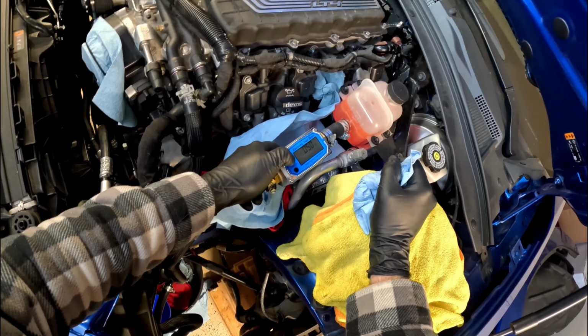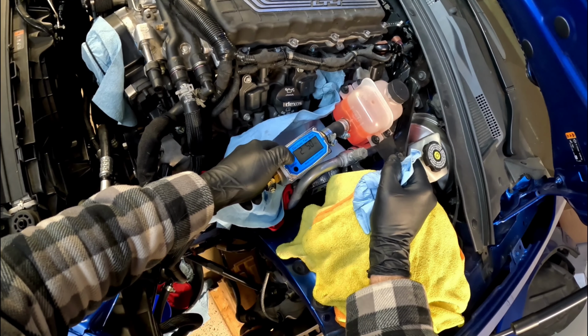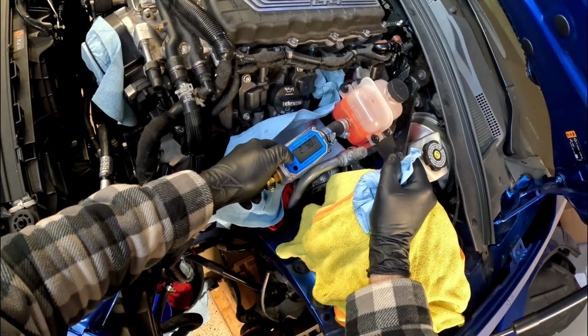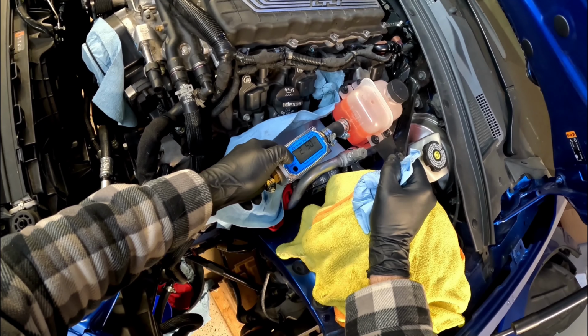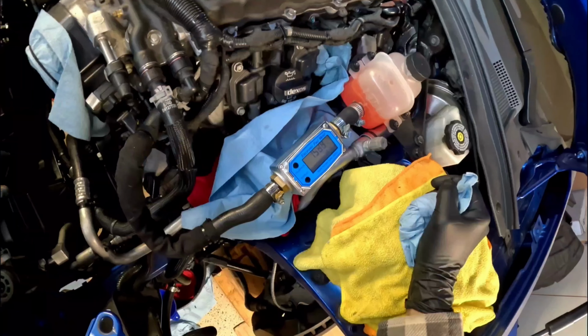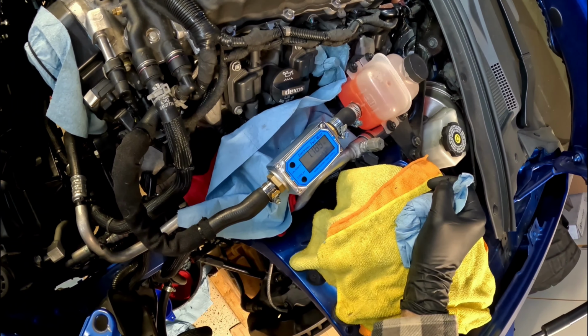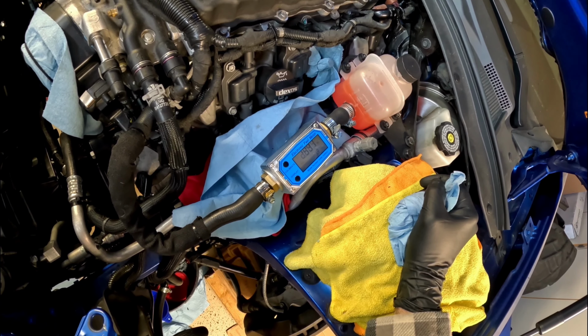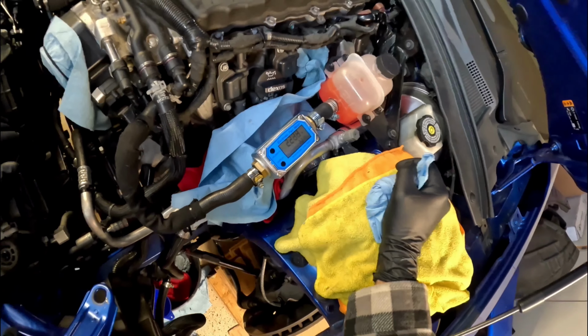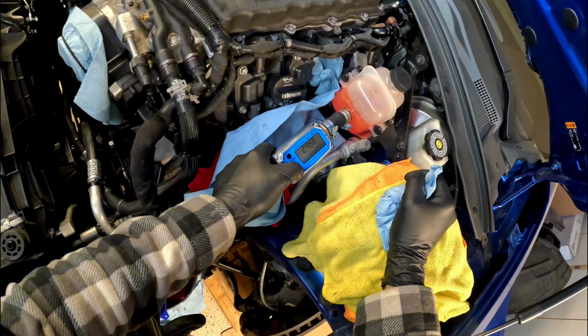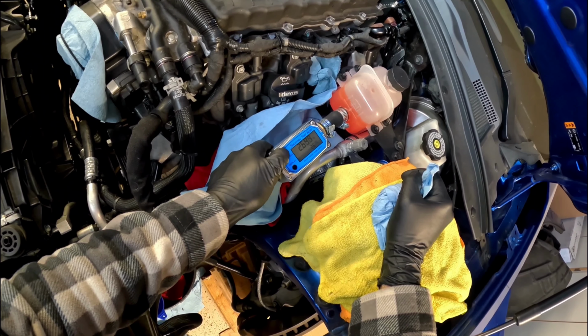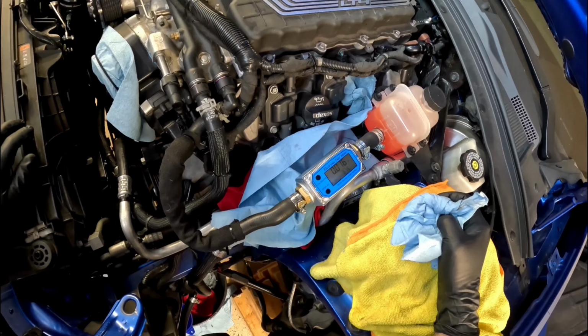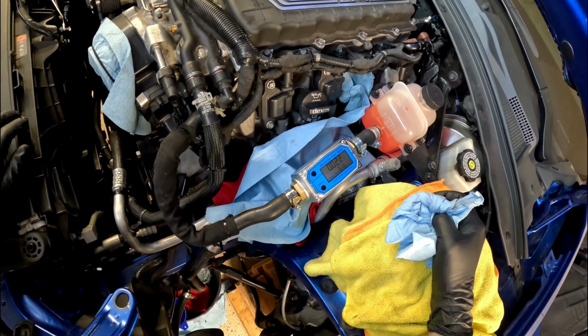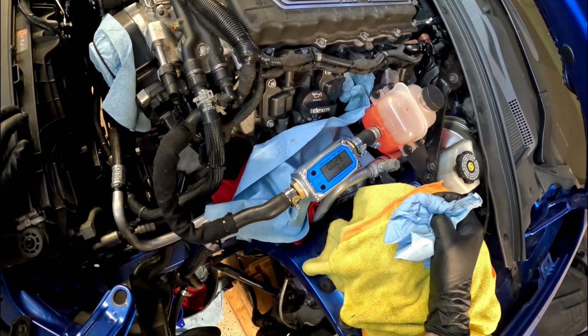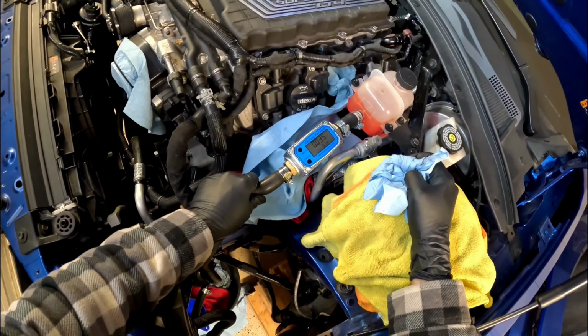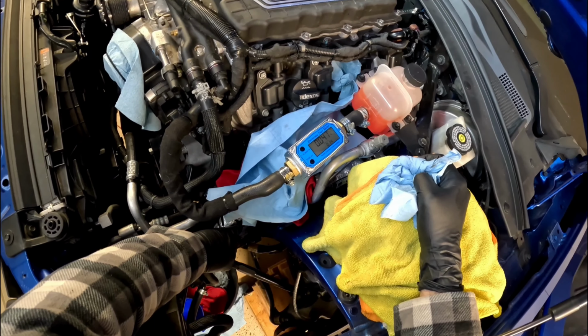Because if I change this up to 2.05 and run the system, you'll see that it shows a much higher flow rate. You can see that it's showing a flow rate much more than before. So you can tell that by changing this conversion factor, or I've seen it referred to as the K factor, it will skew the readings on this meter. I'll go ahead and change this to 1.00, which I believe is what it should be set at, and we'll go ahead and test it, try it again, and see what it looks like.